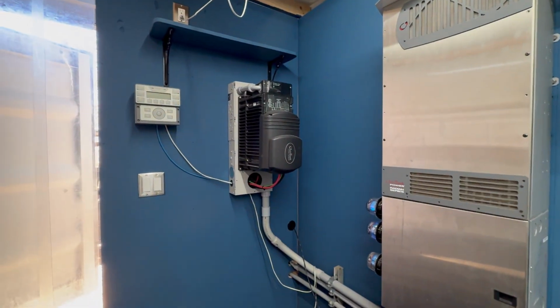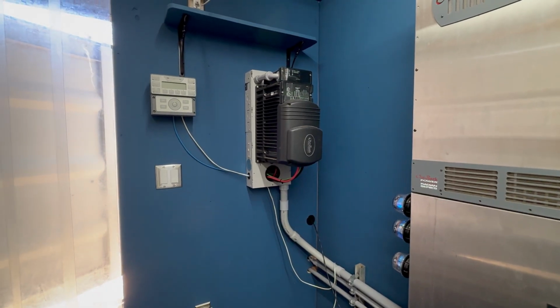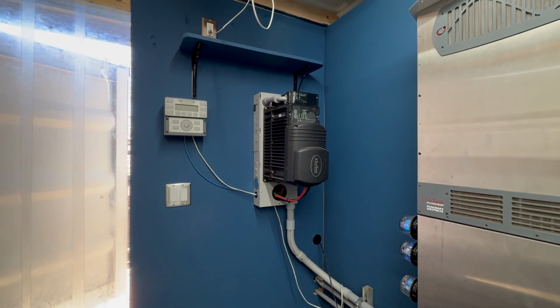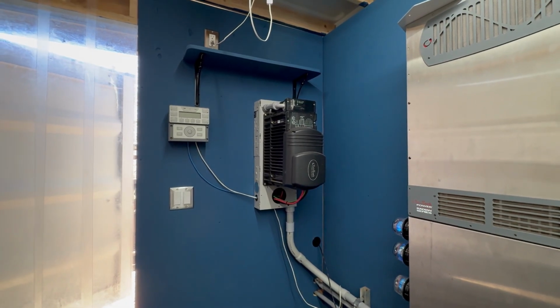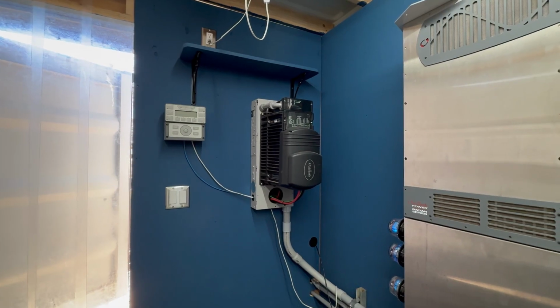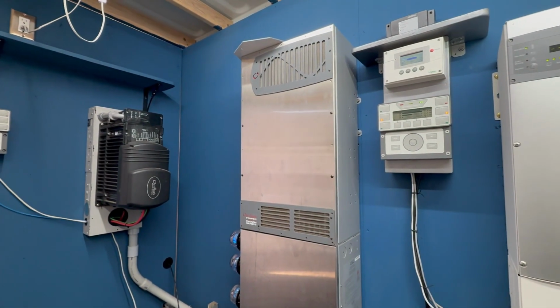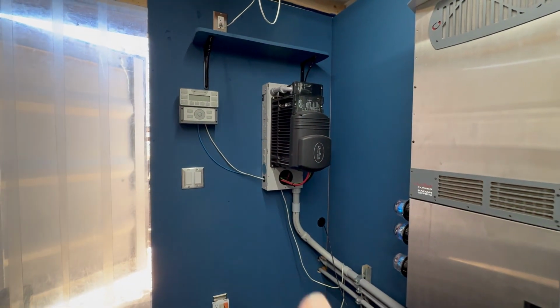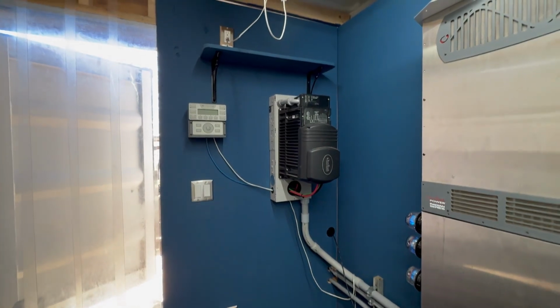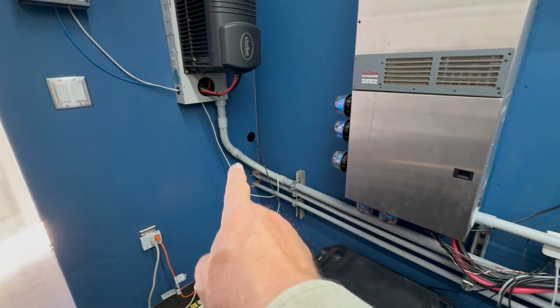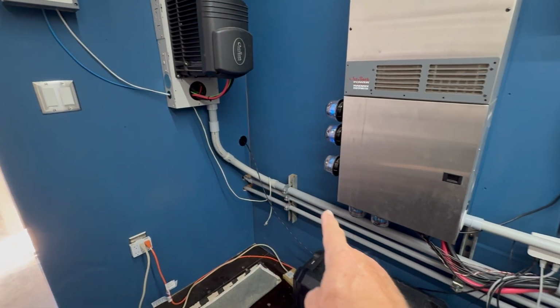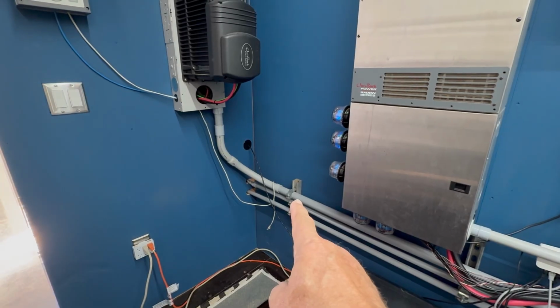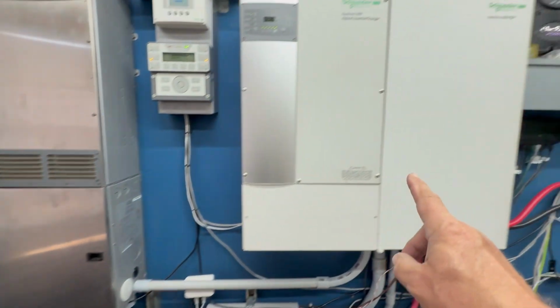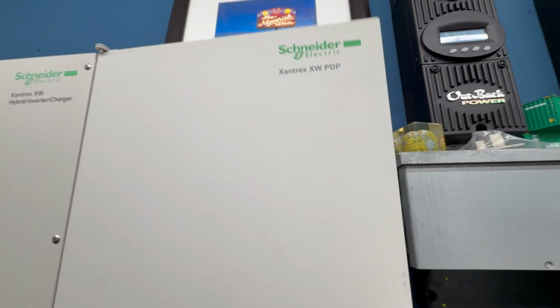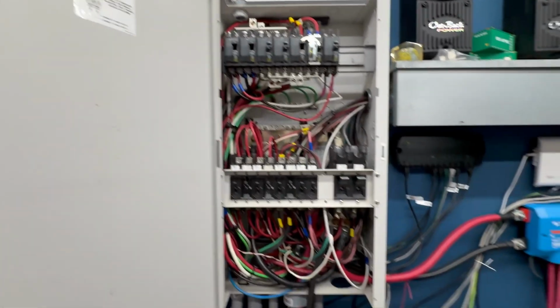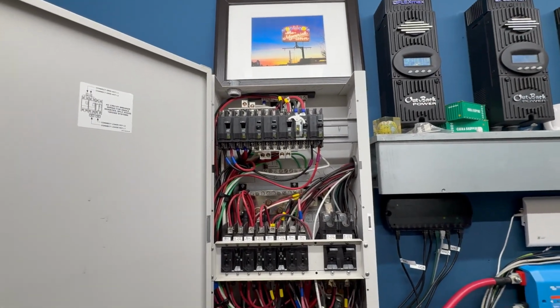And then the FX I haven't used in years. I did wire it up. The concept there was to use it as a chargeverter style device with a Honda 3000 generator. But I also have a Kubota diesel generator, which pairs nicely with the Outback. So I think what I'll do is take down the FX and in its place put the NV Duo. I do have a pipe for, this is DC wire, but I will convert that 1.25 inch conduit for use for the AC input and output, getting me over to this lovely XW PDP power distribution panel, because it has all the DC and AC breakers you could possibly enjoy.